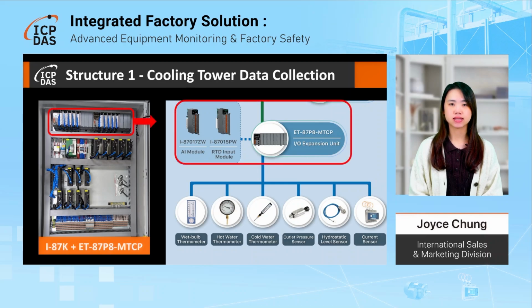In this case, the customer used ICP-DAS I87000 series I/O modules combined with ET-87P8-MTCP I/O expansion unit to collect the data of the cooling tower, including hot water and cold water temperature, wet bulb temperature, outlet pressure, and liquid level, as well as the motor current of the cooling fan.